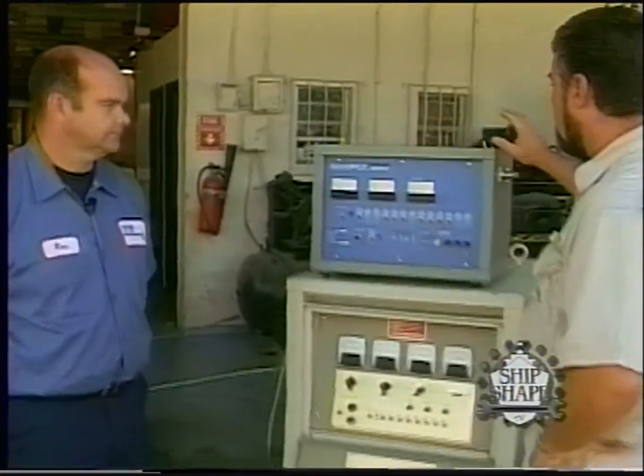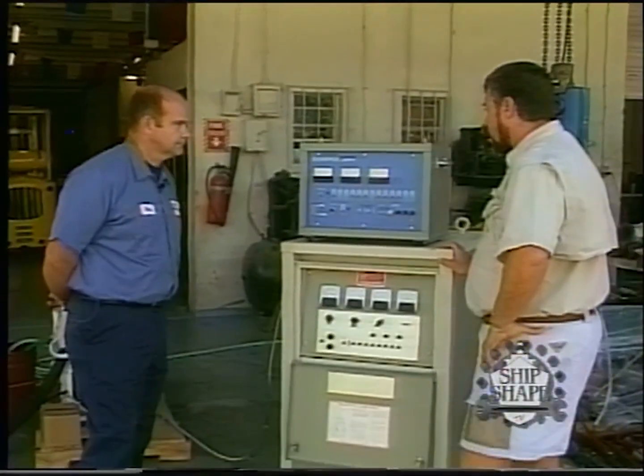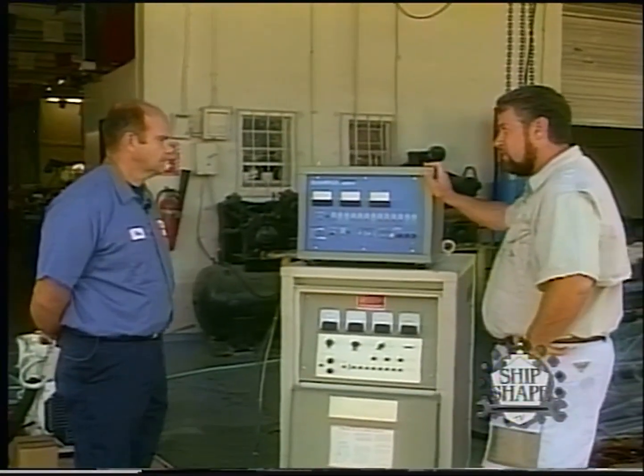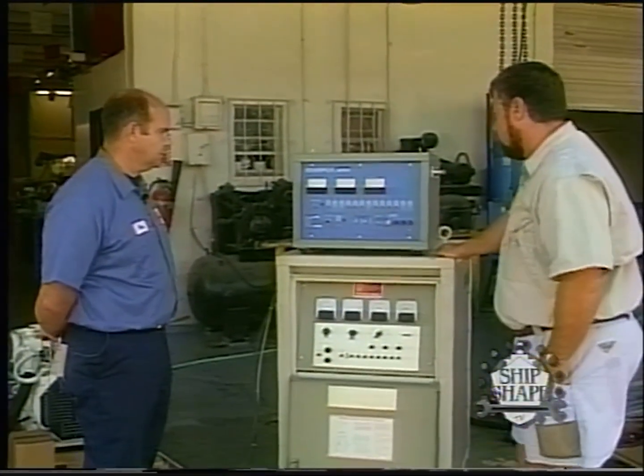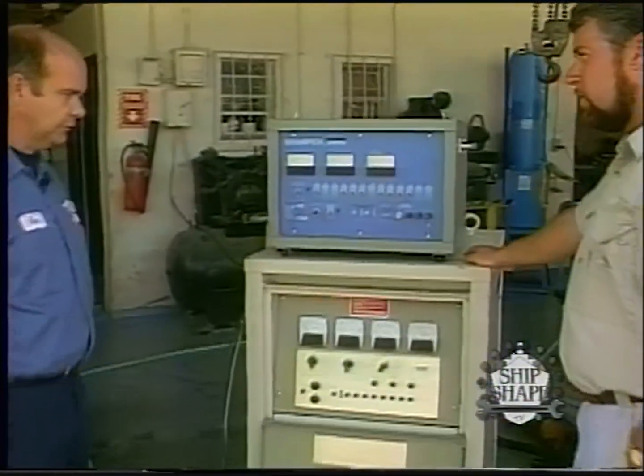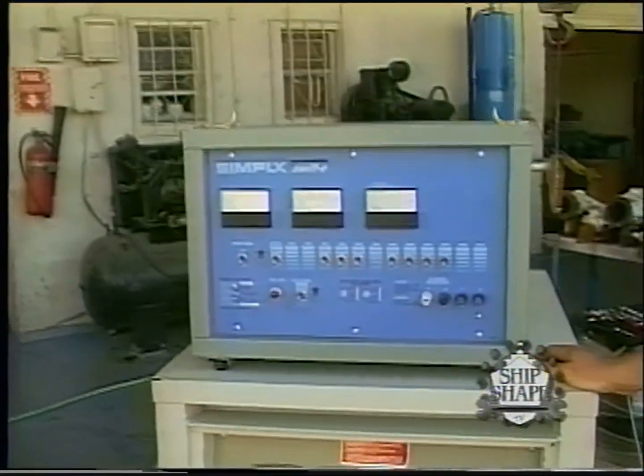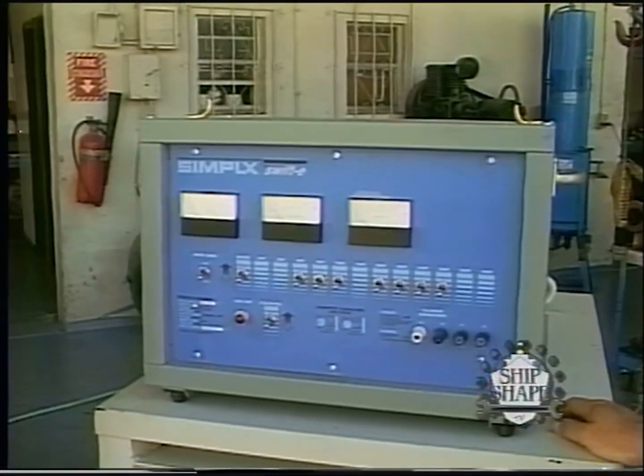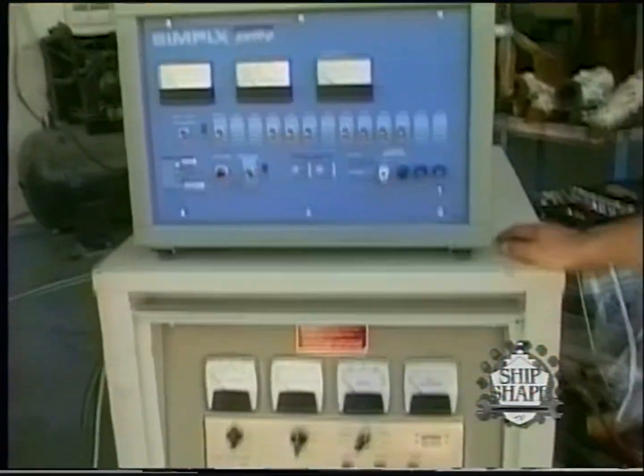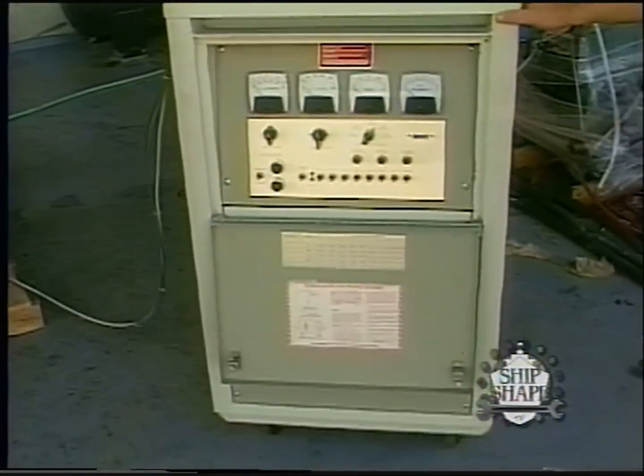We've got a couple of load banks set up here. The top one is a single-phase 10 kW portable load bank, which we normally use on site at a boat to test and diagnose generator problems. The one below is a 40 kW three-phase unit, which we normally use at the shop for testing larger units.